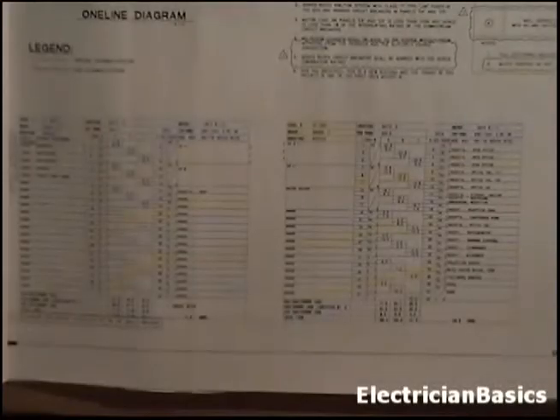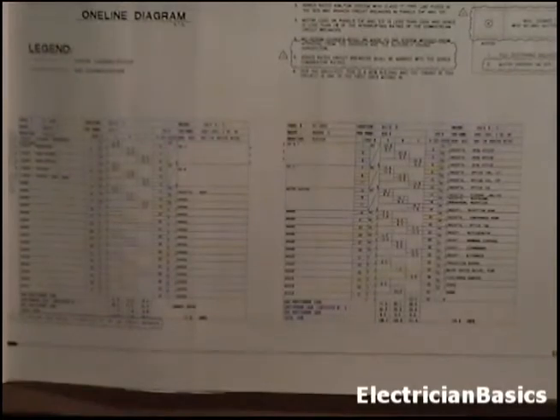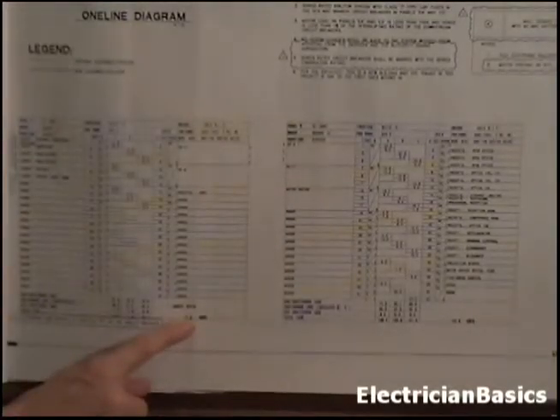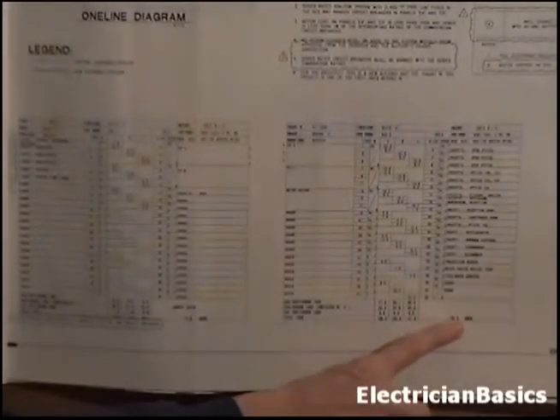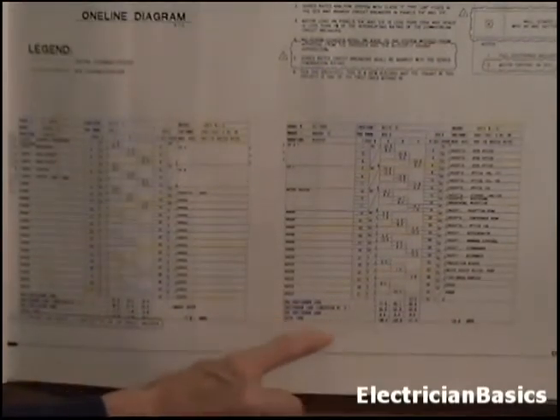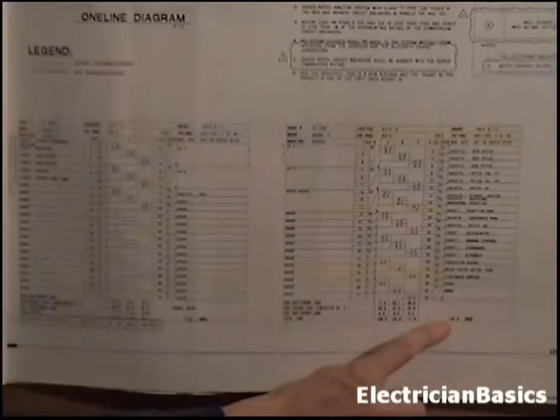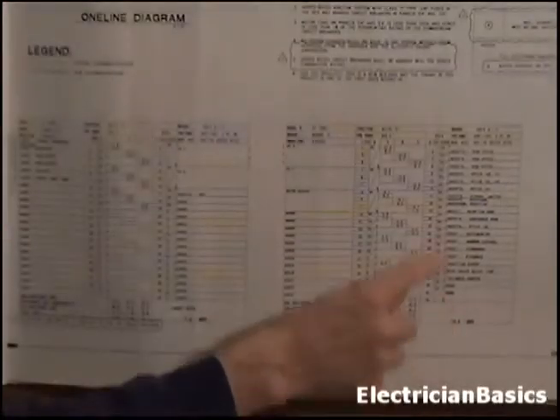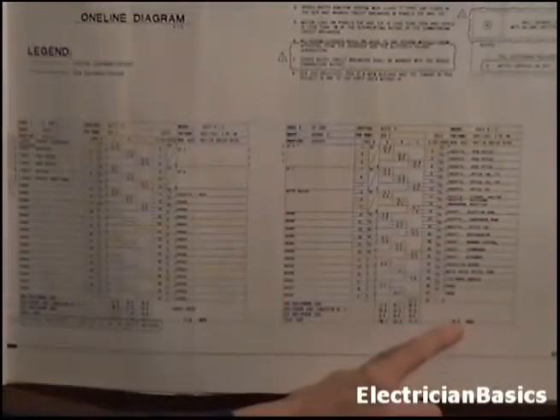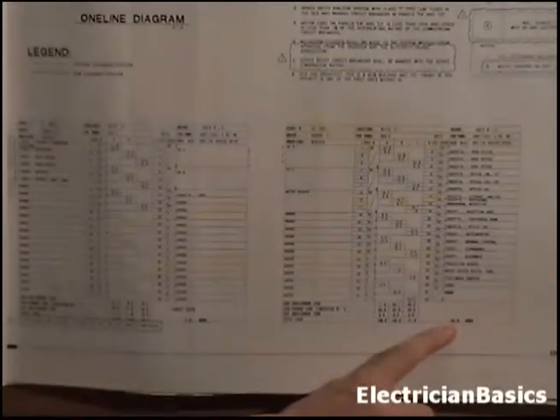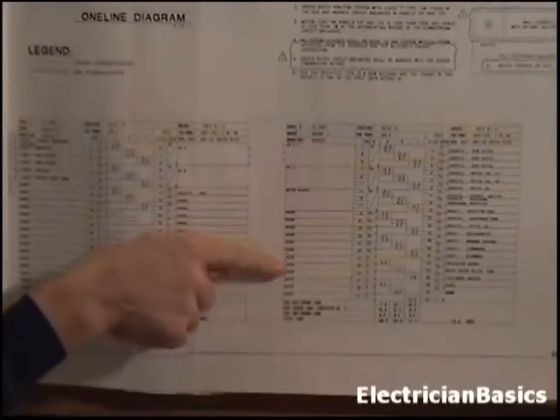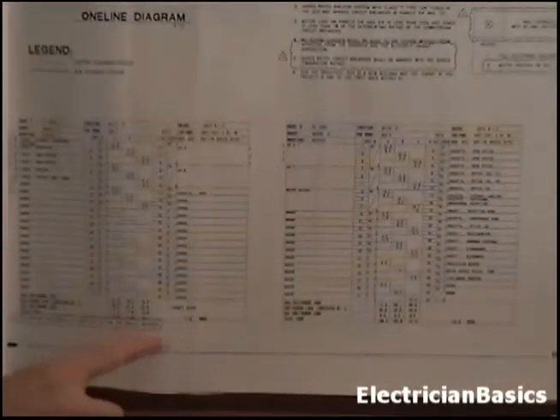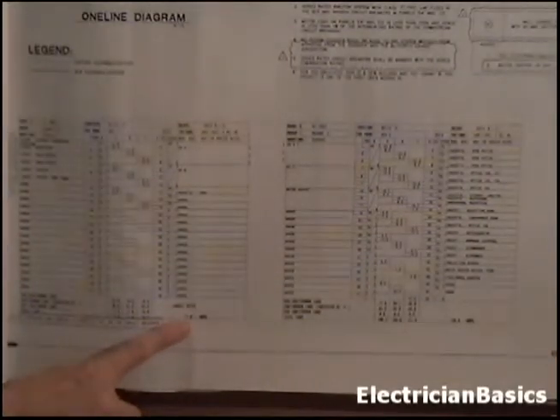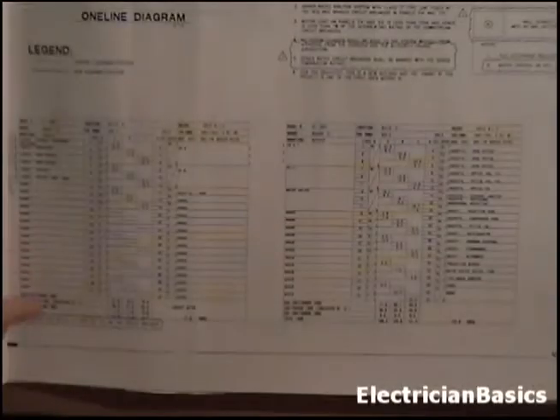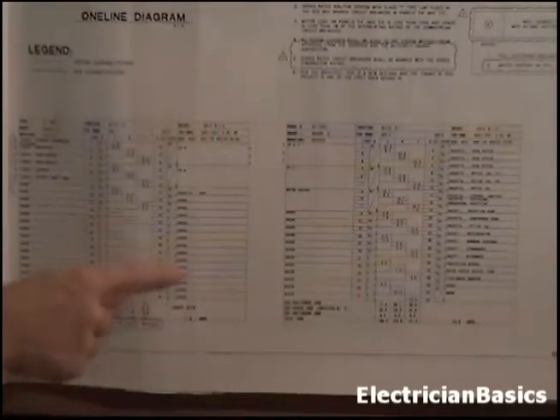Okay, so let's back out a little bit and take a look at both of these panel schedules at the same time. And I just want to point out a couple of things. You need your print in front of you. Right down here, there's a number in this corner and a number in this corner. And if you go over, it says total load. And on panel E5, it's 124.9 amps. We had a 200 amp breaker on this panel, yet we only have basically 125 amps. So that leaves a lot of room for expansion. And of course you look, we've got spare breakers and spaces for more. And on panel E4 we have 77.9, so basically 80 amps, and again a 200 amp breaker. And we have lots of spaces over here and a couple of spares, and mostly spaces over here.